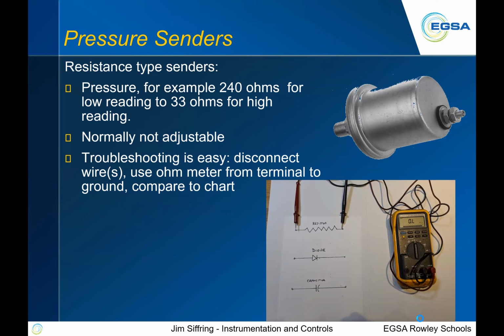Put your ohm meter across it from the metal case to the pin itself that's on there. It should give you some resistance of some kind. If there's no pressure applied, it should read somewhere in the range of 240 ohms. Be careful to disconnect whatever wire is on there, because that may skew your reading. If you apply full pressure, it should read 33. That isn't a set rule. Those resistances may change from device to device, but for this particular one, it's pretty common. So you can use that.